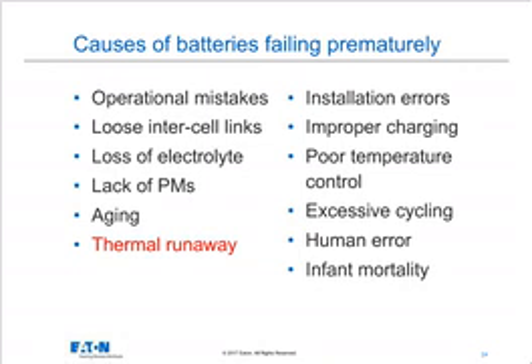The causes of batteries failing prematurely, there's several of them here. I won't drag you through all of them. But loose intercell links or loose connections on the battery, a lack of battery maintenance. In red there you see the big one, which is thermal runaway. And many of you, if you've seen this happen, it's a pretty dramatic event. Basically, if I have a large industrial battery that for some reason, maybe it's due to overcharging, maybe it's ambient over temperature, but the battery gets a little bit warm. And when the battery starts to get hot, it draws more current.